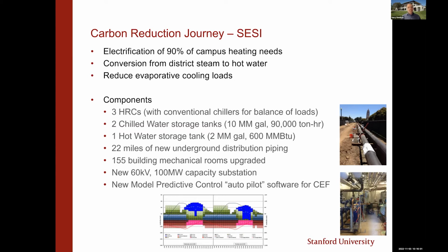We put in a lot of thermal energy storage, both chilled water and hot water. That helps us with load flattening, but also gives us more flexibility on how we operate our assets. We can run them at their sweet spots. We don't have to swing them as much because the storage can take up a lot of the variability.